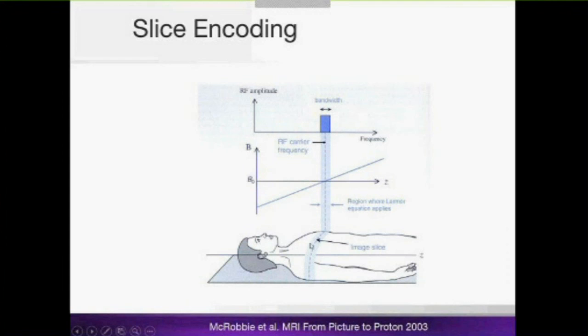To select only a single slice, we apply a slice-selection gradient so that the magnetic field — and therefore the Larmor frequency — varies along the patient's body. We then apply an electromagnetic wave whose frequency matches the Larmor frequency only within the desired slice. In the other slices this frequency is not the local Larmor frequency, so the resonance criterion is not met and they are not excited. Only in the selected slice is the resonance criterion satisfied, and that is how we excite only that slice.